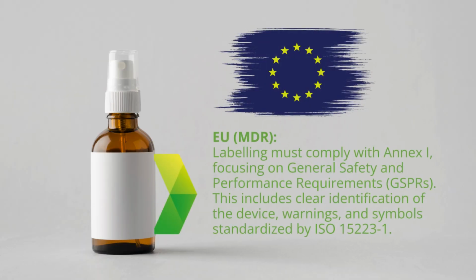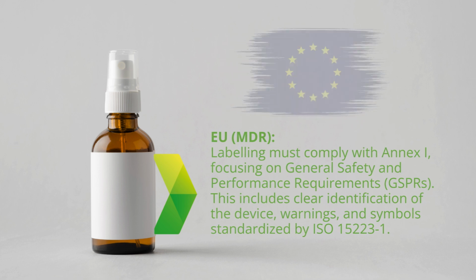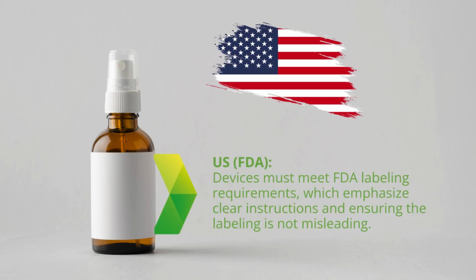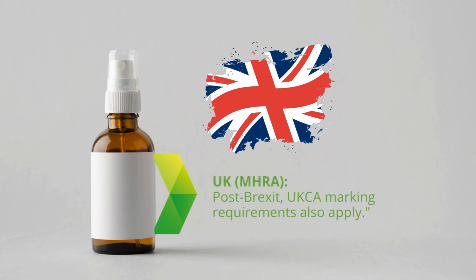Different regions have their own requirements for medical device labeling. Let's look at the key ones. 1. EU MDR: labeling must comply with Annex I, focusing on general safety and performance requirements, GSPRs. This includes clear identification of the device, warnings, and symbols standardized by ISO 15223-1. 2. US FDA: devices must meet FDA labeling requirements, which emphasize clear instructions and ensuring the labeling is not misleading. 3. UK MHRA: post-Brexit, UKCA marking requirements also apply.